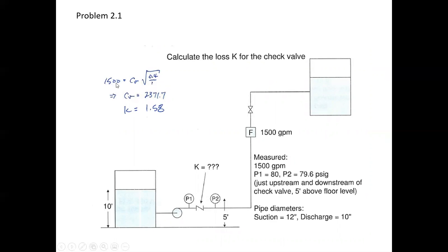The calculation is pretty trivial, but this is the valve equation. Flow is CV times the square root of delta P in PSI divided by specific gravity. And notice there is a geometry factor, F sub P, but when everything's the same diameter, the geometry factor is 1. So you just do the math, and guess what? You get the same value. Okay.